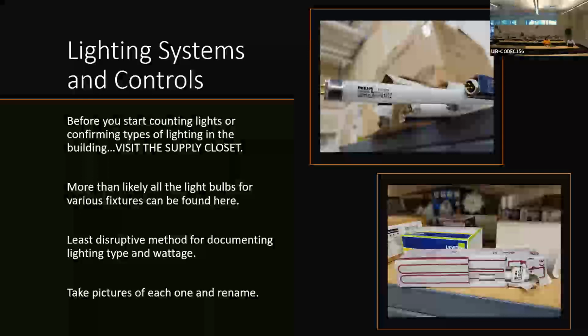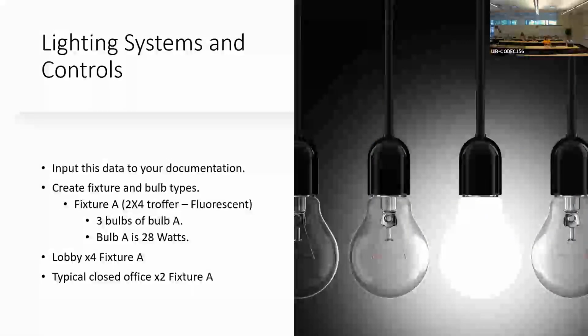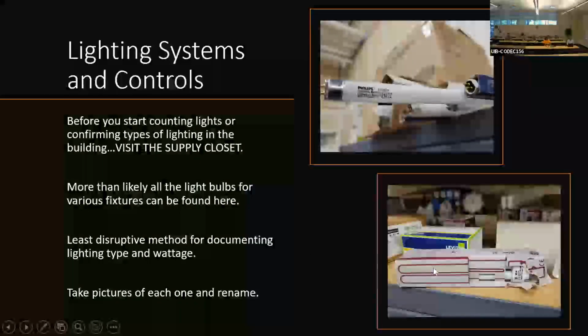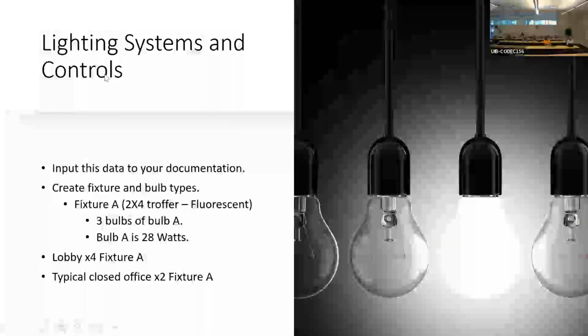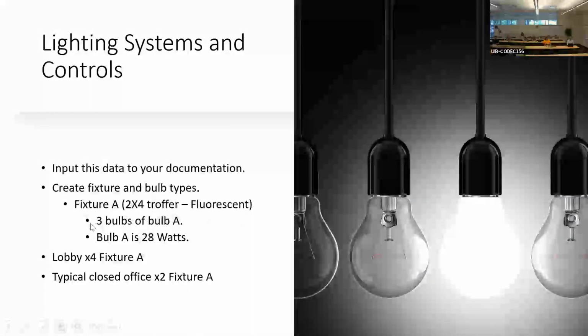I recommend doing both, and then I like to rename things for nomenclature, so I'll have bulb A and fixture A. This would be bulb A and this would be bulb B, and this typically goes on a 2x4 recessed troffer. So fixture A, a 2x4 troffer, is fluorescent with 3 bulbs of bulb A, meaning fixture A is 3 times 28 watts. Then when I go to the lobby, I have 4 of fixture A, that's what I write down as I'm walking through. Doing this organization and nomenclature beforehand makes walking through the building a lot simpler.